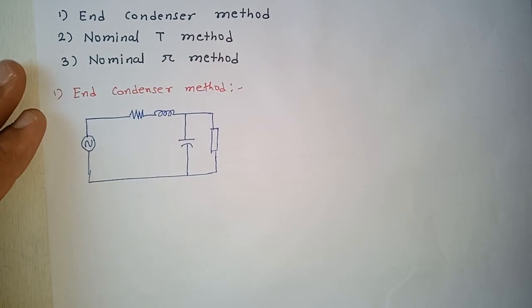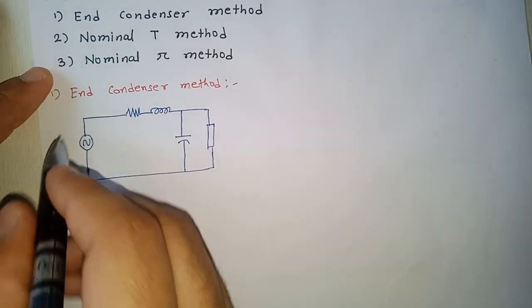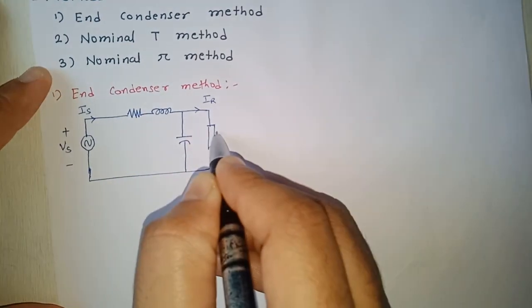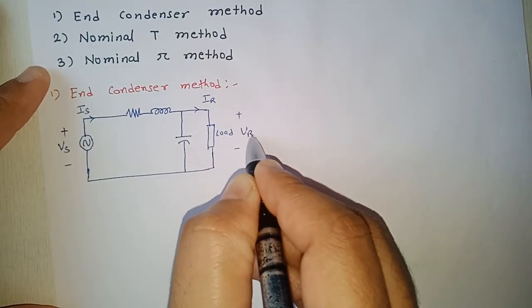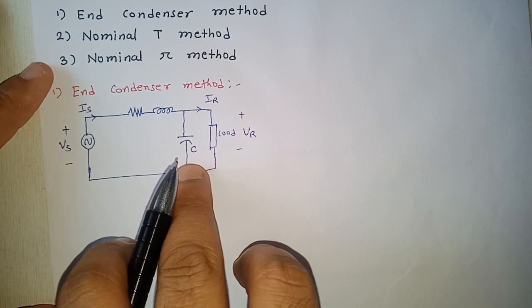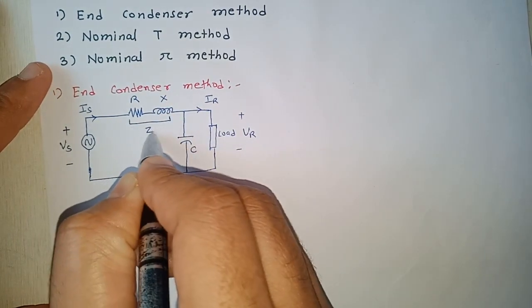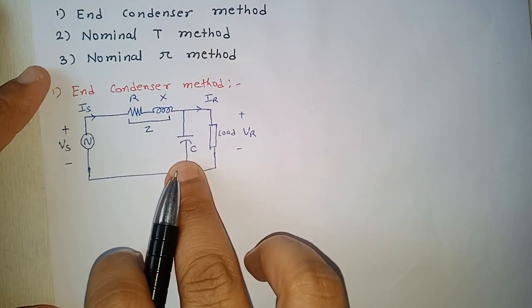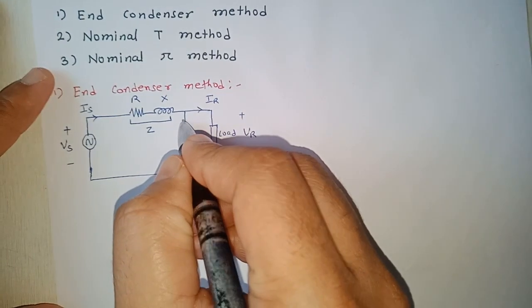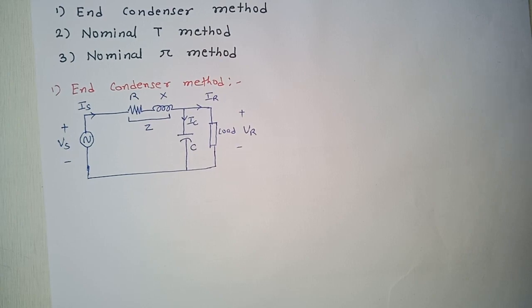This is the per-phase circuit diagram of the medium transmission line using the end condenser method. Vs is the sending end voltage, Is is the sending end current, Ir is the receiving end current, and Vr is the voltage across the load. The capacitor (condenser) is located at the receiving end — that is why this method is called the end condenser method. R is resistance, X is reactance, together forming impedance Z. The capacitor current is Ic.